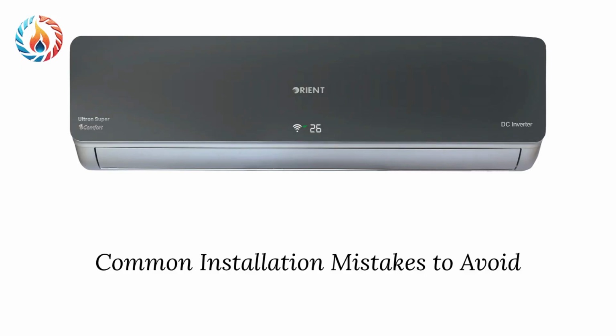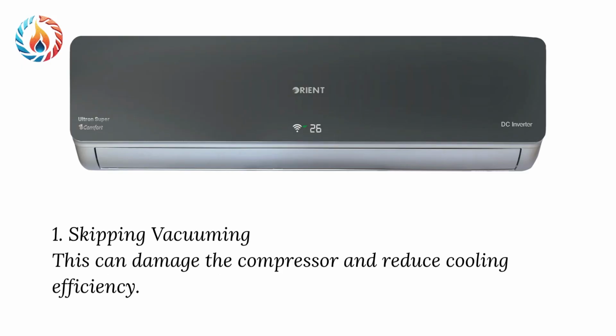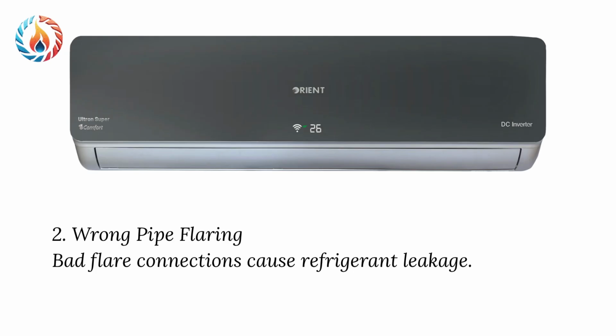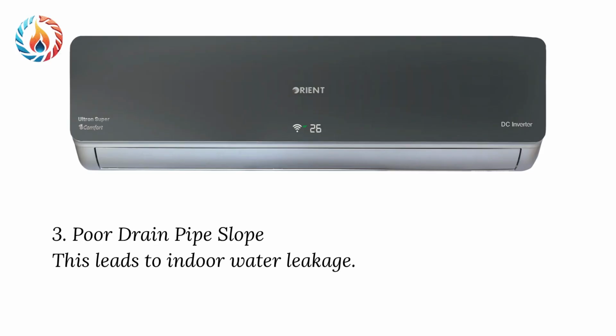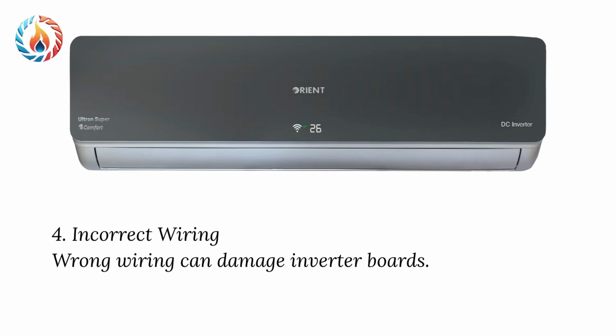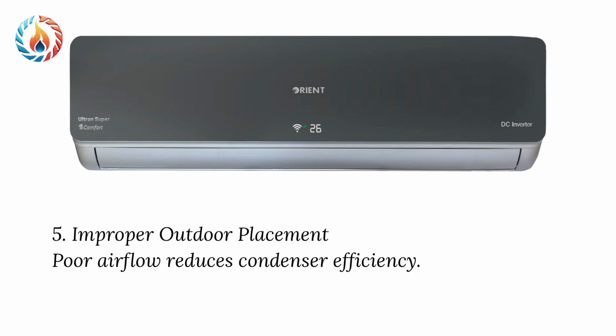Common installation mistakes to avoid. 1. Skipping vacuuming. This can damage the compressor and reduce cooling efficiency. 2. Wrong pipe flaring. Bad flare connections cause refrigerant leakage. 3. Poor drain pipe slope. This leads to indoor water leakage. 4. Incorrect wiring. Wrong wiring can damage inverter boards. 5. Improper outdoor placement. Poor airflow reduces condenser efficiency.